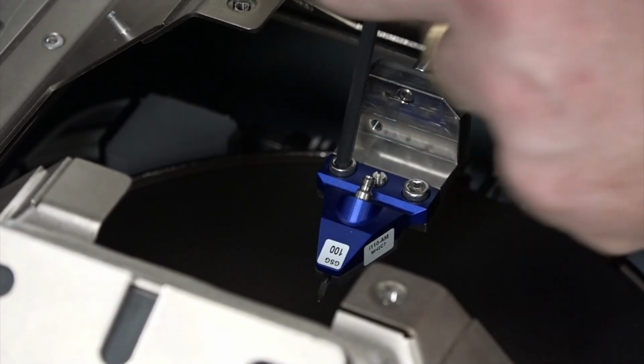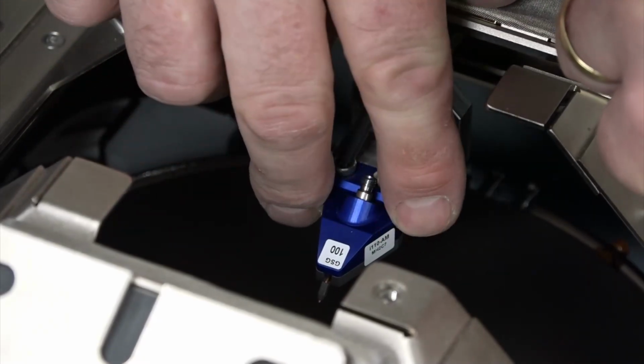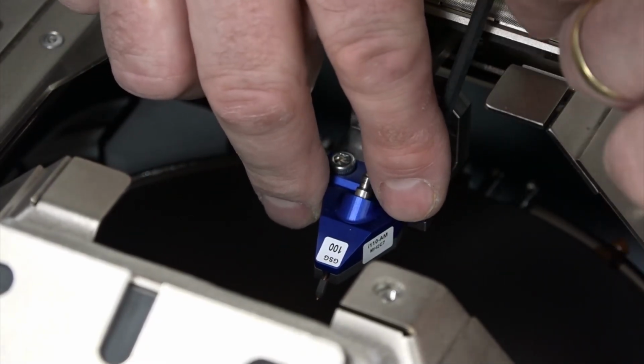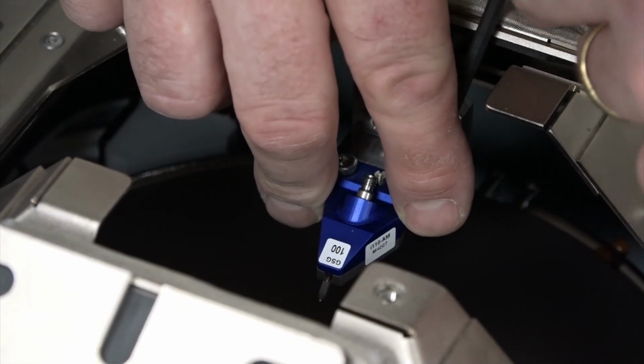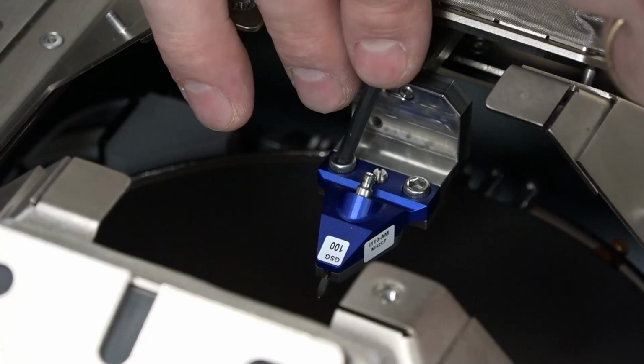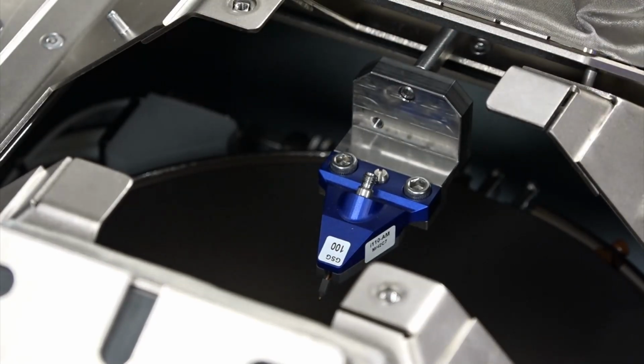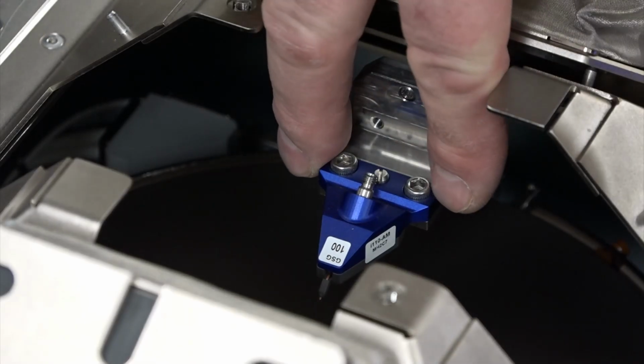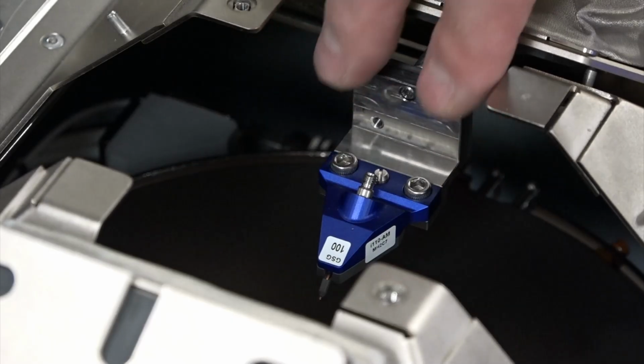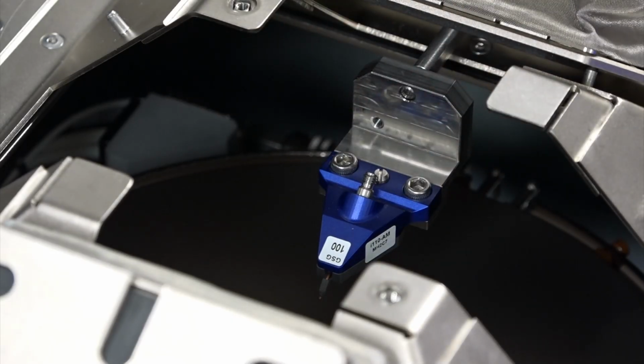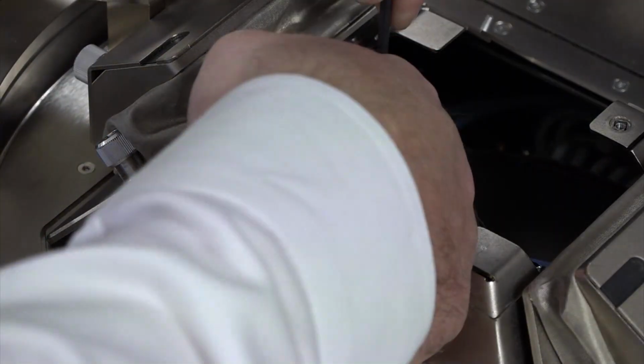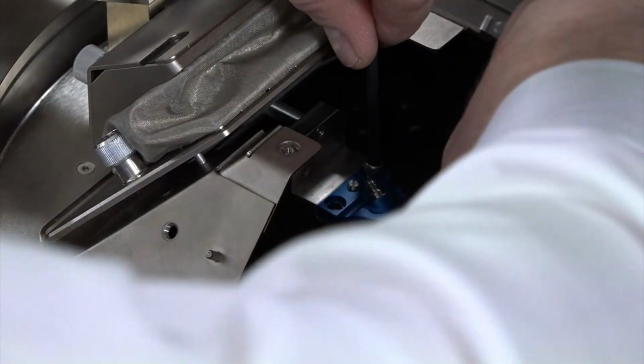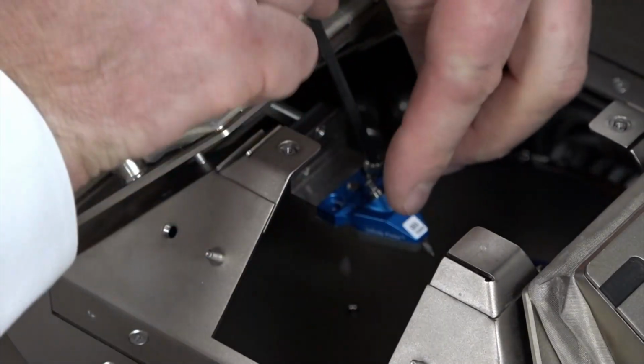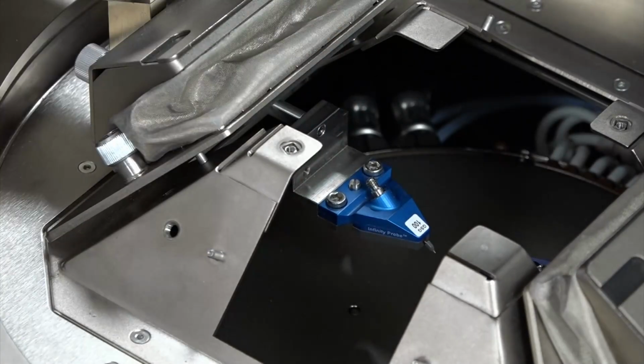Now, one thing I sometimes do when I do this, and it's difficult to show, is I push the probe into the back of the mount, which makes it square. There is a little bit of play in there, so you can adjust it. Likewise, if you put the probe on and you notice there is a significant angle across the probe tips, you can slacken these screws and rotate the probe in the opposite orientation until you get the rotation of the probe tips looking the same as the wafer rotation. Okay, let's do the same thing for the other side. Okay, so I'm going to secure the left-hand probe. Do the same kind of thing. I'm not sure if you can see me. Let me try and put my hands around the other way. So that's both my probes secured.